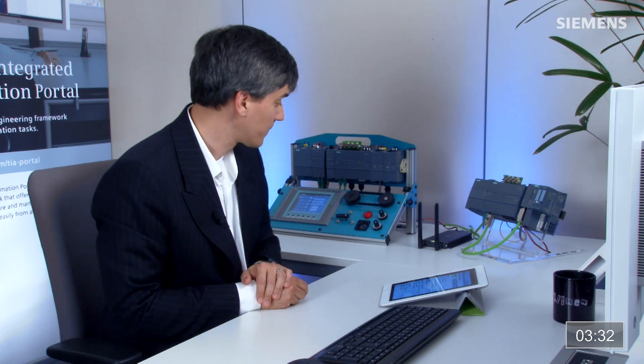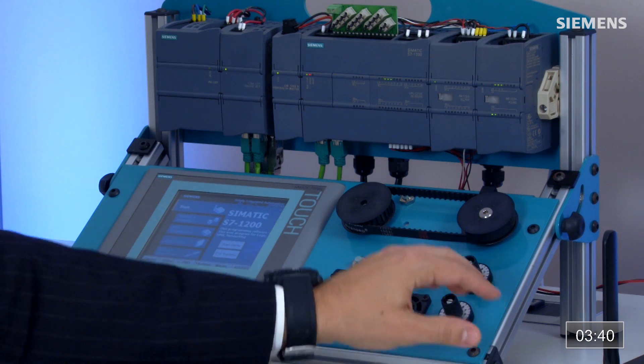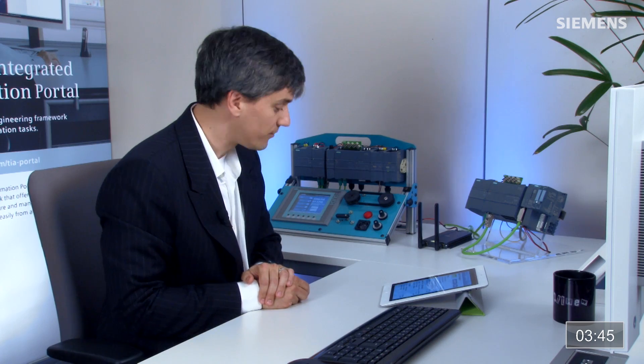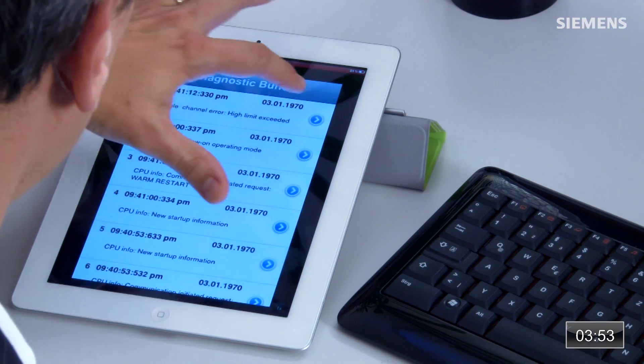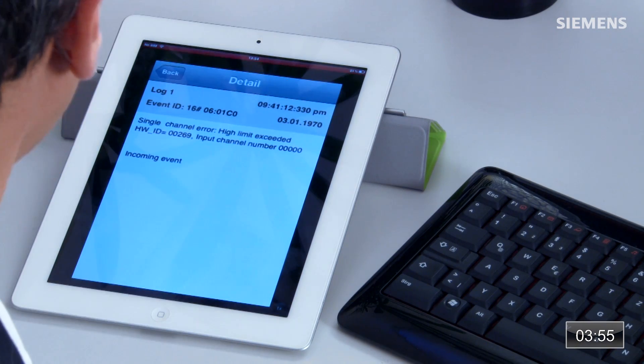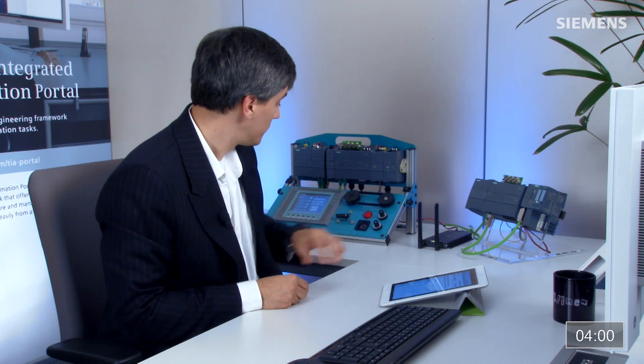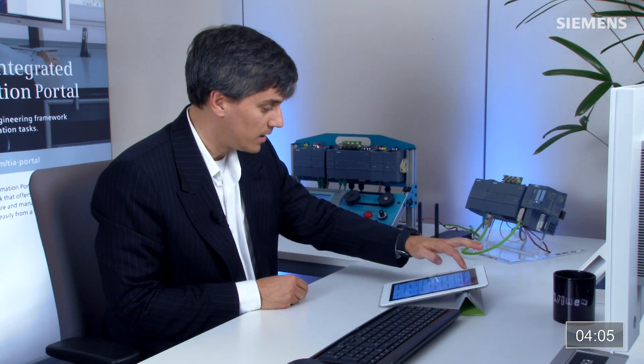How about diagnostics? Currently I have a potentiometer wired into this analog card, and anything above 5 volts is going to be a high limit exceeded condition. Let me turn it above 5 volts. Now you can see the LEDs — we have a registered fault. The analog card updates here in a few seconds. Now it has — there is an error message. Click on the diagnostic buffer: the first message is 'single channel error — high limit exceeded.' That is exactly correct. Let me solve the problem, and now the control system has resolved it. Going back to the original screen, there is absolutely no problem with the analog card at this point.